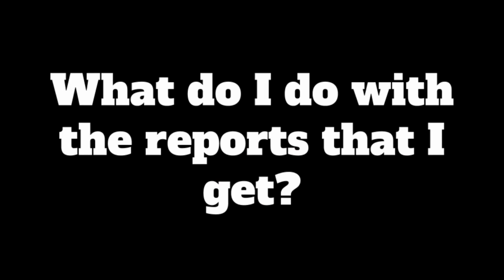What do I do with the reports that I get? Every time that we do a fire suppression inspection, we create a report. These reports have to be kept on your premises for a period of 3 years. We also keep a copy of it, so if you use us and you need these reports sent to you, we can email them over to you. All of our reports have pictures and so forth of our inspection process. It's also referenced in the Virginia Statewide Fire Prevention Code 901.6.2 that we shall report all of our findings during the course of our inspections to the local authority having jurisdiction, so that they can ensure that your business is safe and your property is safe. So you want to keep a record of those inspections for 3 years.